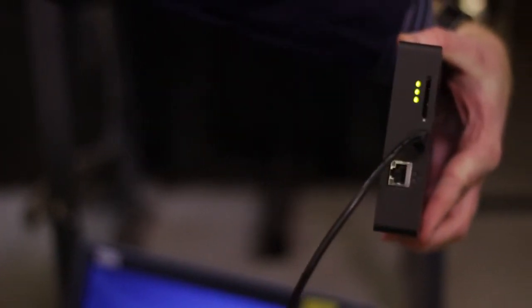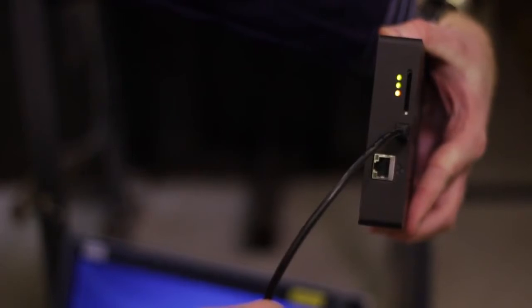So, first we connect the Cable Data Collector to the laptop. This powers it up via its USB port. No need for an external power supply. Check the LEDs. The top 2 lights will go green when the unit is ready. The orange light shows you need to connect the phase reference transformer. More about this in a second.